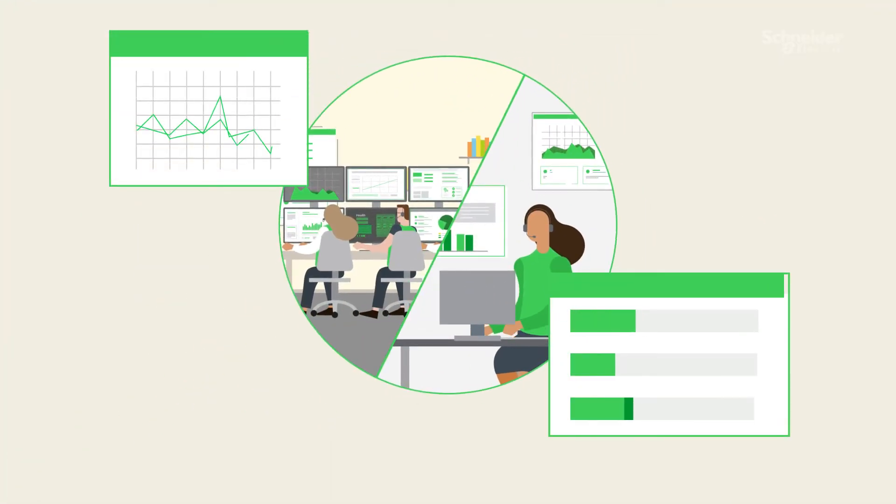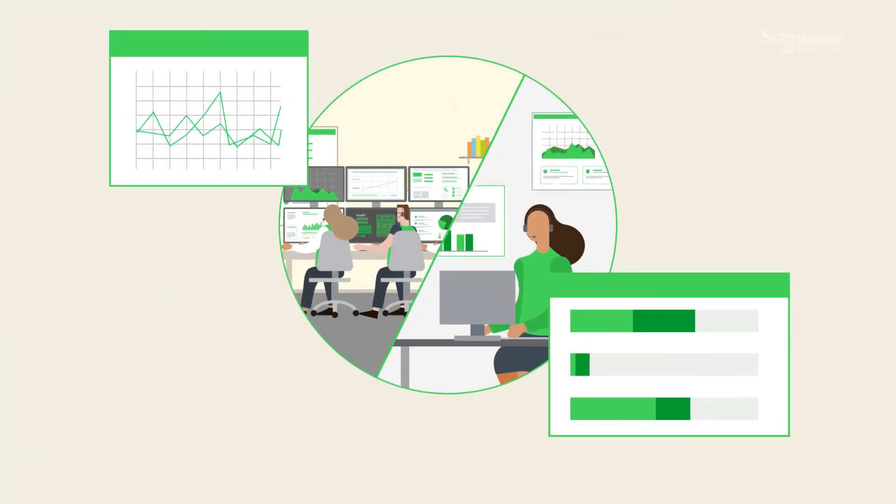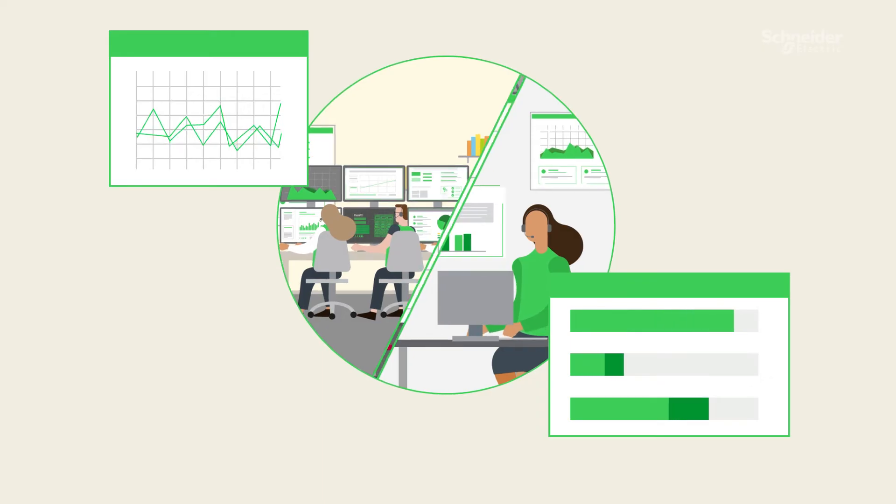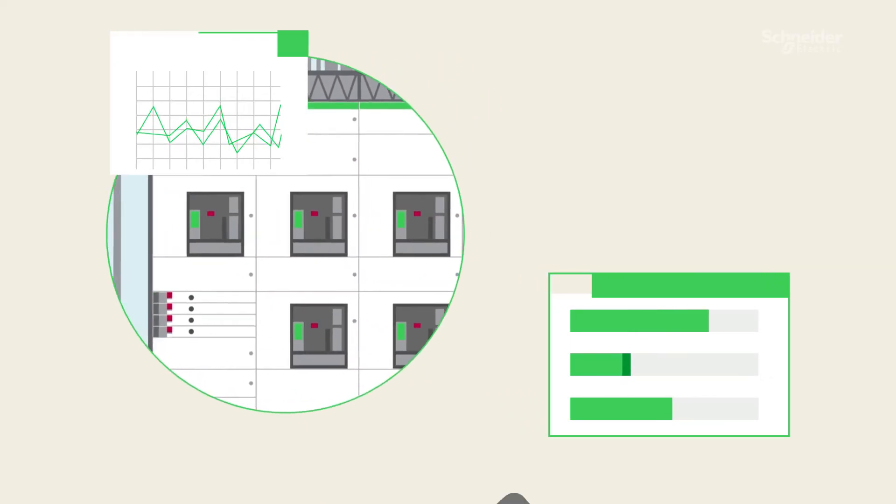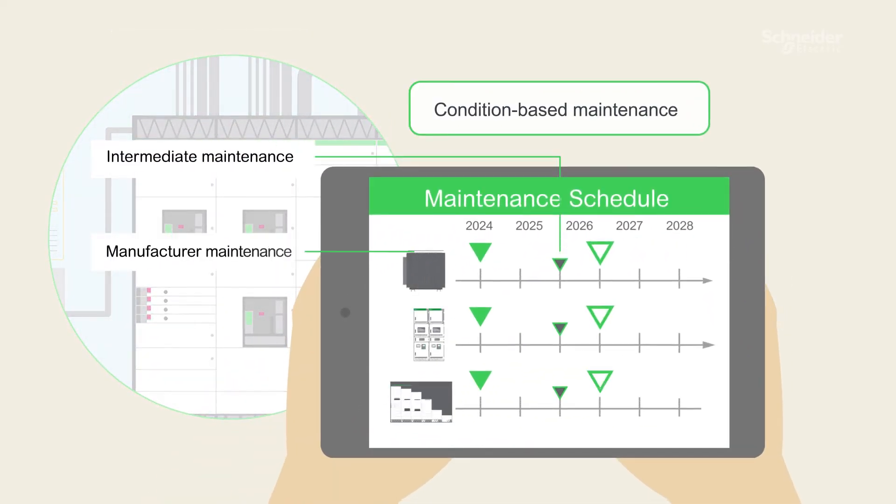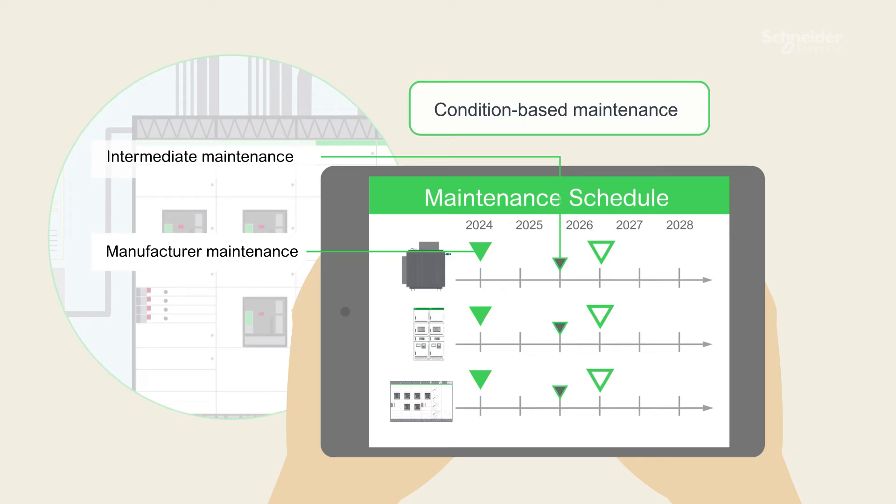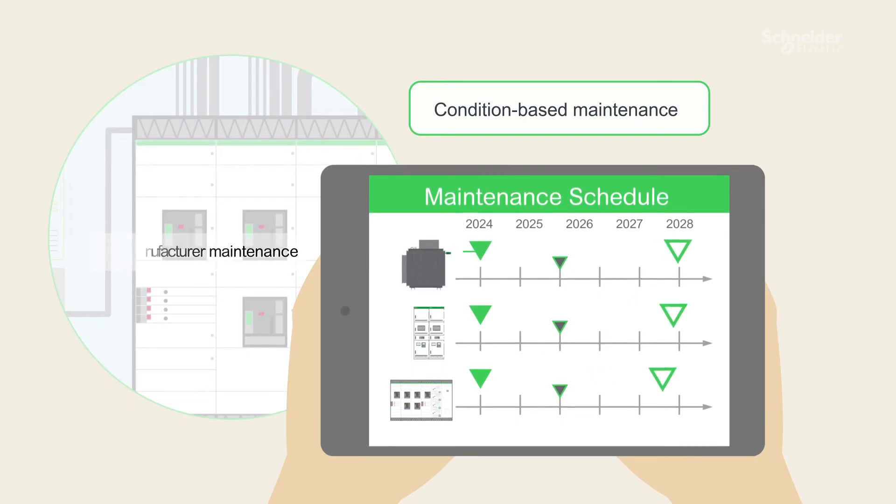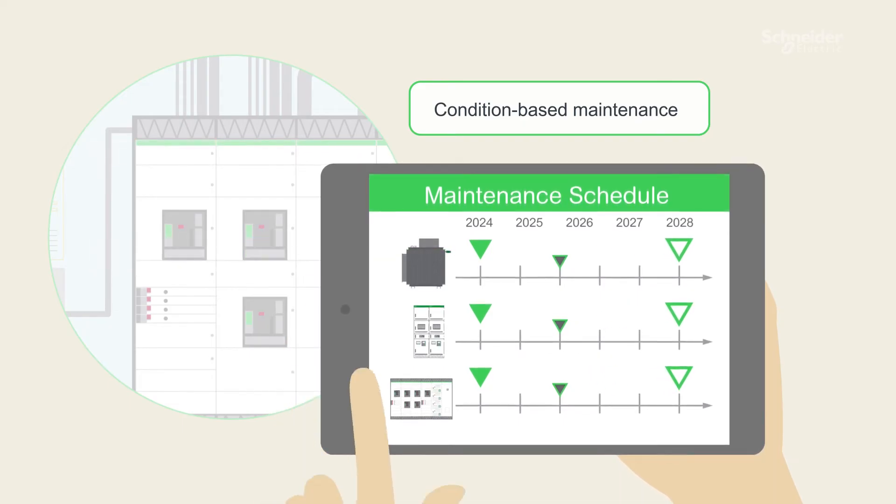Through continuous asset monitoring and field data collection, the frequency of manufacturer maintenance can be extended compared to traditional calendar-based service plans, from three years up to five, by switching to condition-based maintenance.